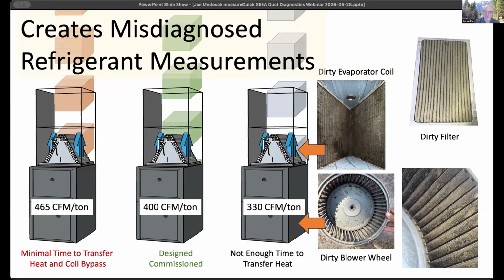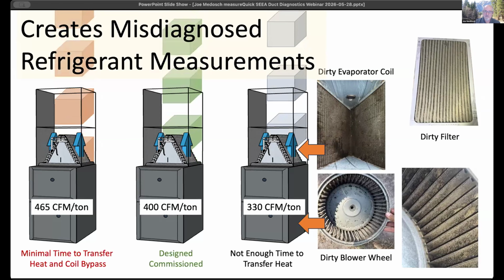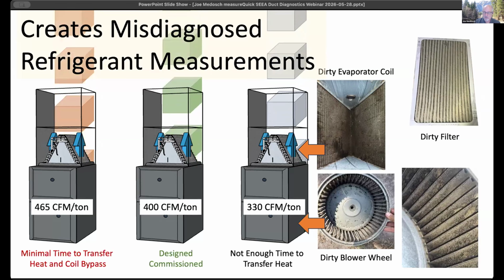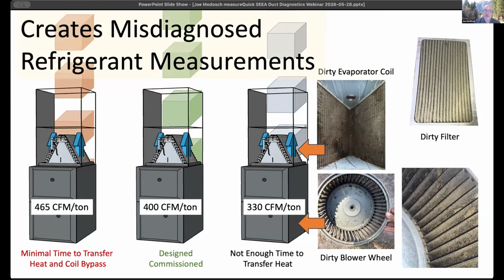This is one of the greatest problems we have in our industry: people think everything's fixed with refrigerant, either more or less. So again, a fundamental rule is you need to make sure you not just confirm everything is clean and working, including the coil outside, but that you've measured what your airflow is.